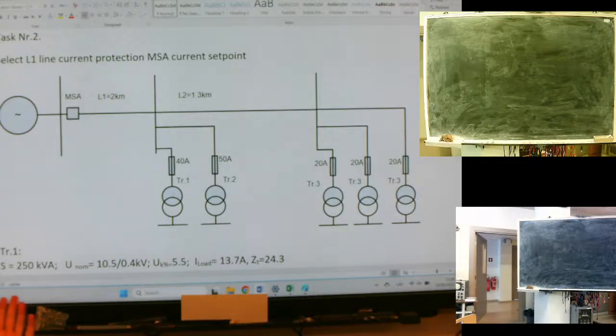Because we just discussed, okay, we have this current protection of line 1. All what we have done previously is to understand what is the maximal possible normal operation current for line number 1 to calculate over current protection set point. It is clear, okay, but we want to check and we want to make a fault to calculate the fault current value. What is the location of fault? What fault we will check? What fault location we will choose?